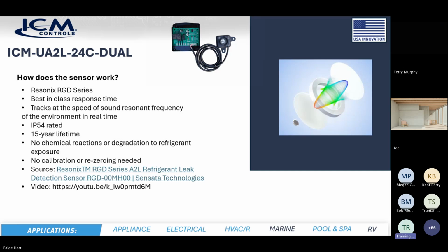This sensor is IP54 rated, which is an industry certification. It's got a 15-year lifetime. You don't have to worry about chemical reaction because it's monitoring the change in the sound of the airspace when the refrigerant enters that airspace. You don't have to worry about it being degraded by chemical exposure or exposure to refrigerants, like some of the other types that sense the actual refrigerant itself, which can get saturated if you have a huge leak. This one's a little bit different. So there's no calibration or re-zeroing needed. Because again, it's all based on the principle of resonant frequency of sound in that environment. So when there's no gas present, the sound looks to the sensor a certain way. The minute the gas enters, it changes, and the sensor picks that change up.